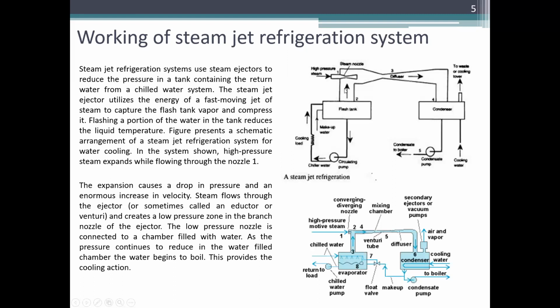Ito tayo sa taas. Ito, baka maano kayo. Okay? Internet yan. Ito yung sa book. The expansion causes a drop in pressure and an enormous increase in velocity. Steam flows through the ejector, sometimes called an eductor or venturi, and creates a low pressure zone in the branch nozzle of the ejector. Same topic din sa power plant, yung steam, yung jet condenser. Check na yun. The low pressure nozzle is connected to a chamber filled with water. As the pressure continues to reduce in the water-filled chamber, the water begins to boil. This provides the cooling action.